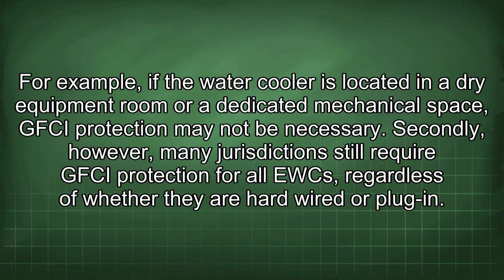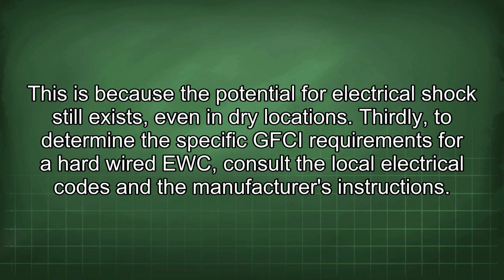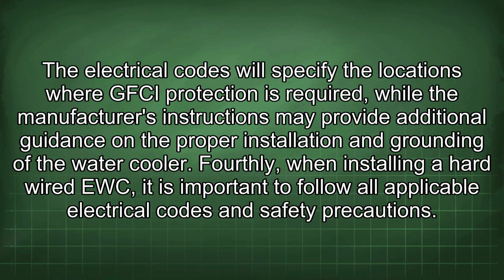For example, if the water cooler is located in a dry equipment room or a dedicated mechanical space, GFCI protection may not be necessary. Secondly, however, many jurisdictions still require GFCI protection for all EWCs, regardless of whether they are hardwired or plug-in. This is because the potential for electrical shock still exists, even in dry locations. Thirdly, to determine the specific GFCI requirements for a hardwired EWC, consult the local electrical codes and the manufacturer's instructions. The electrical codes will specify the locations where GFCI protection is required, while the manufacturer's instructions may provide additional guidance on proper installation and grounding of the water cooler.